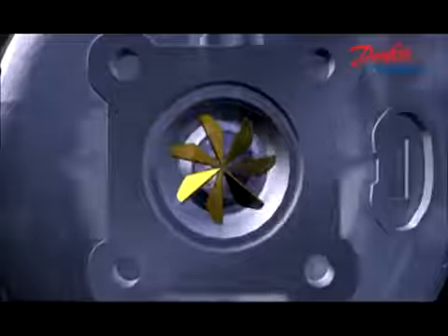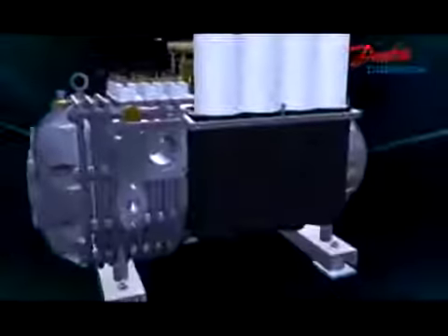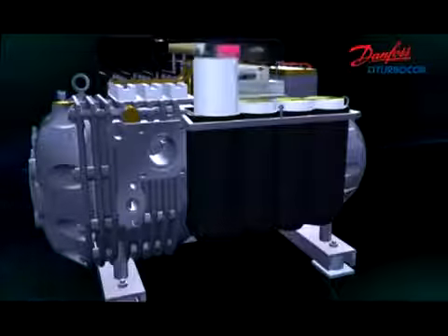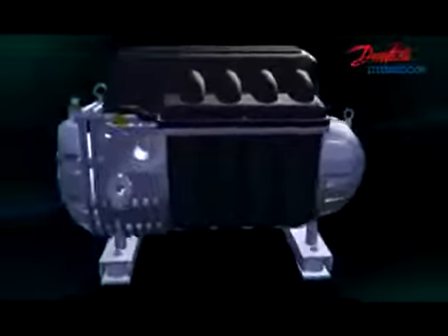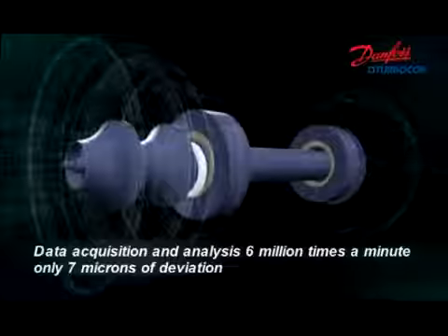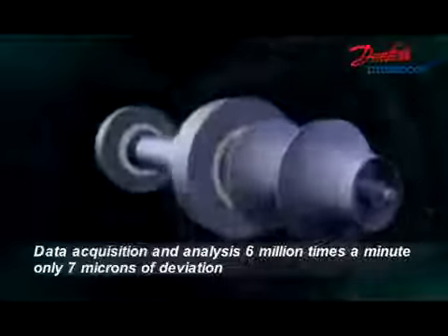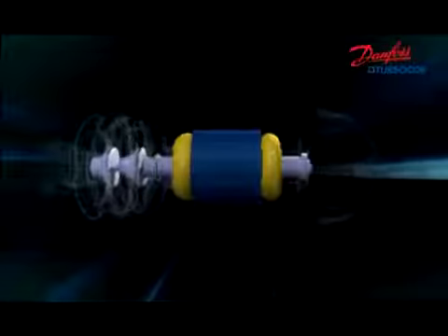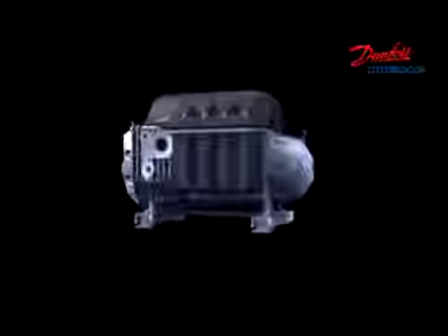Electromagnetic levitation bearings are powered by pulse width modulation amplifiers to maximize efficiency. The bearing and sensors communicate and reposition the shaft digitally and keep the position deviation less than 7 microns. Magnetic levitation bearings make it possible to provide a totally oil-free design for air conditioning and process cooling applications. It eliminates all limitations with efficiency degradation caused by lubricant oil and makes the unit run with high performance and saves more than 50% maintenance cost.